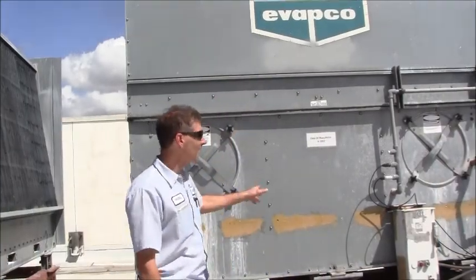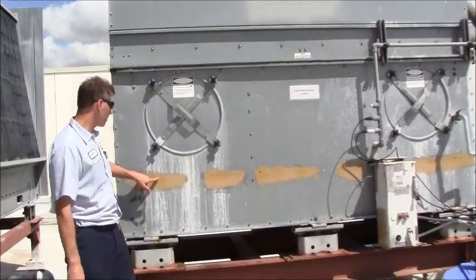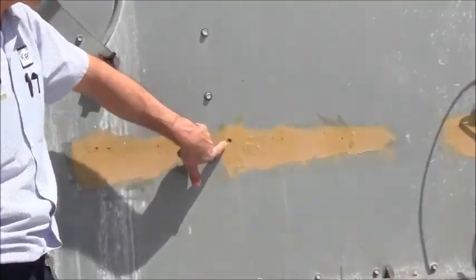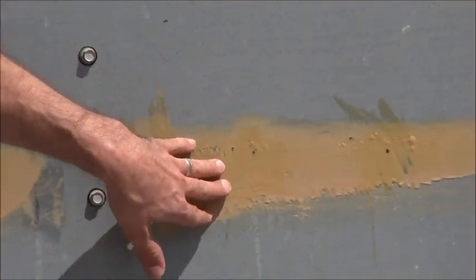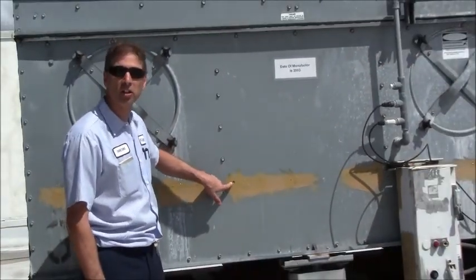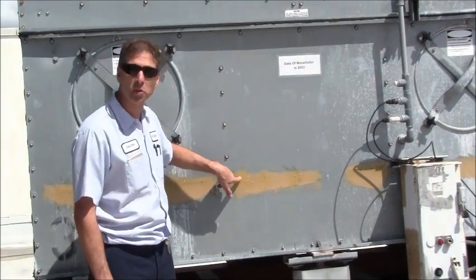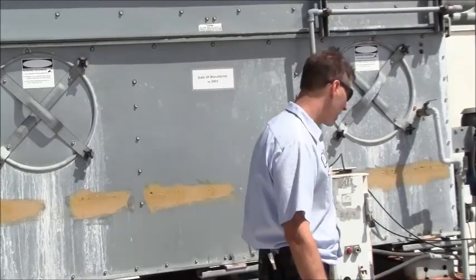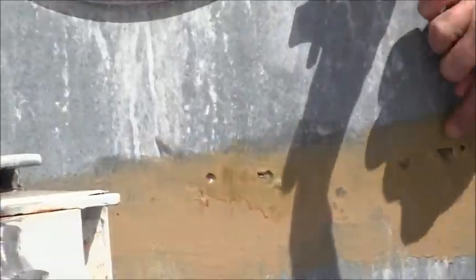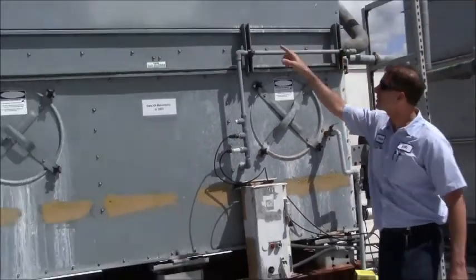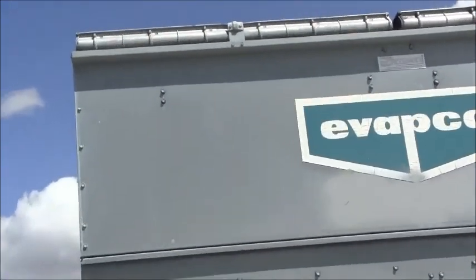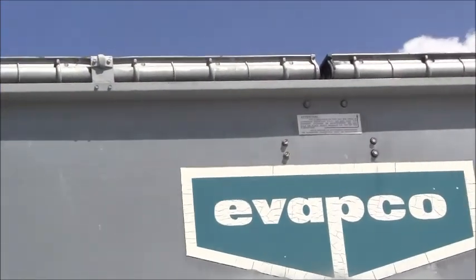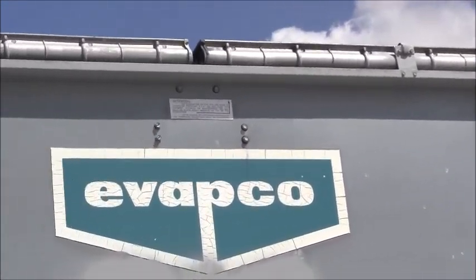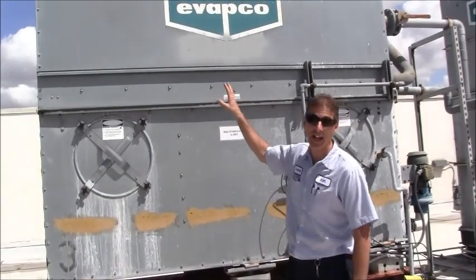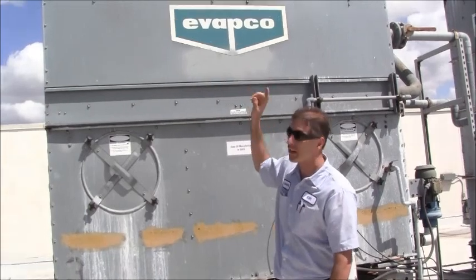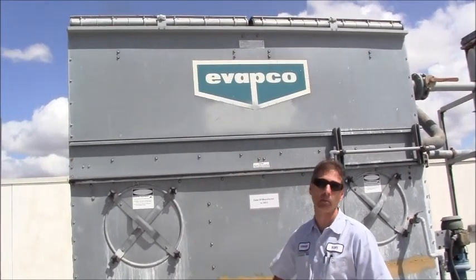All right, so here we are on tower SP number 3. We've done some repairs where the holes were coming through, but here you can see the hole is too big for us with the epoxy—the tan material we were using. So we ordered another product called DuraPatch, and we'll show you what that looks like once we put it on. It's bad here, and I've also got some bad sections over here that I want to cure up. Now let me take your attention over to the top, over here—you can see that now is looking really good after we've sanded it down and prepped it, then used the cold galvanic spray with zinc, and that looks a lot better. So I'll give you some before-and-afters of how that looked and cleaned up really nice compared to where we were.